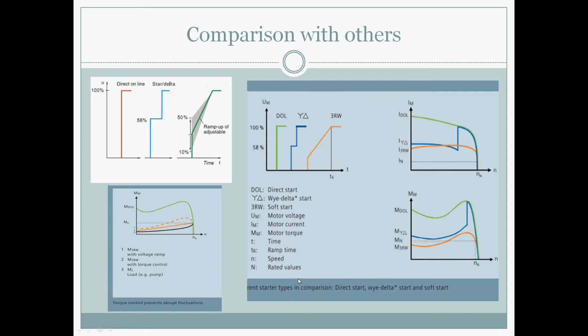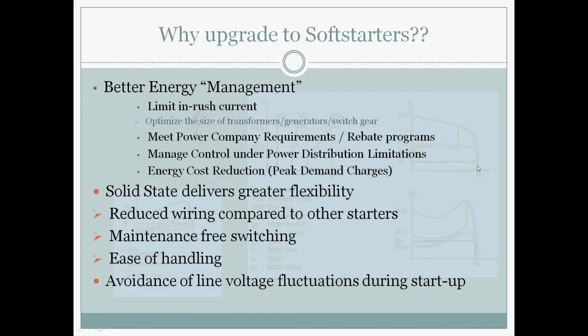Now here is a current comparison by starter type: direct online, Y delta, and soft starter. It is a Y delta one, this is direct online, and this is the soft starter one. Same thing, same feature. The soft starter gives a very decent and regulated amount of current while starting and stopping.